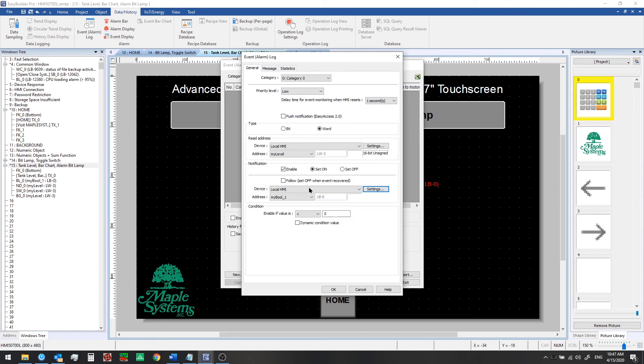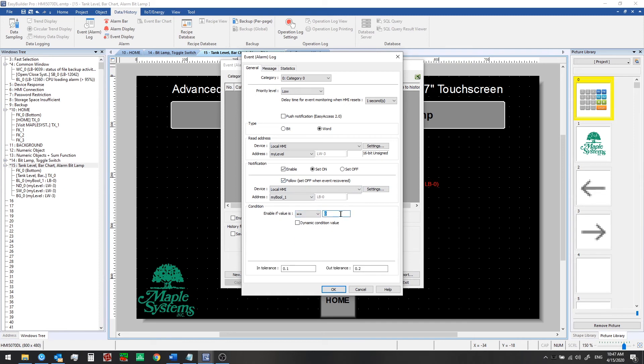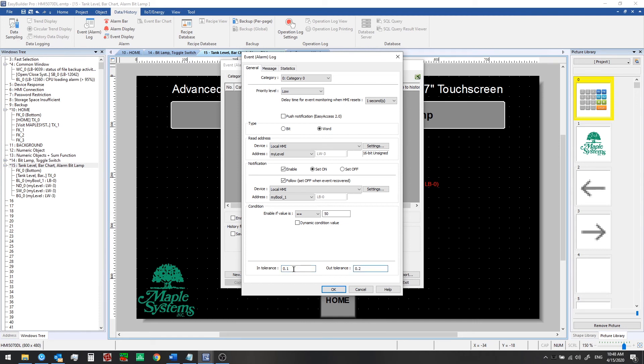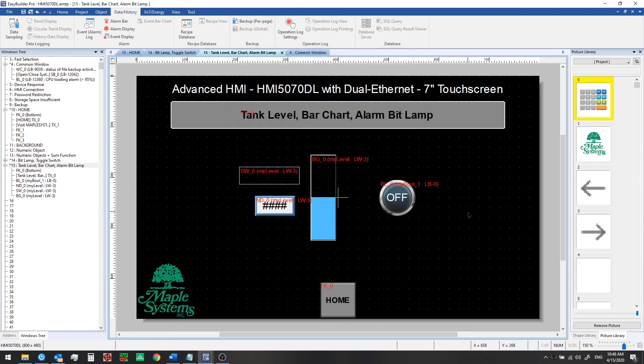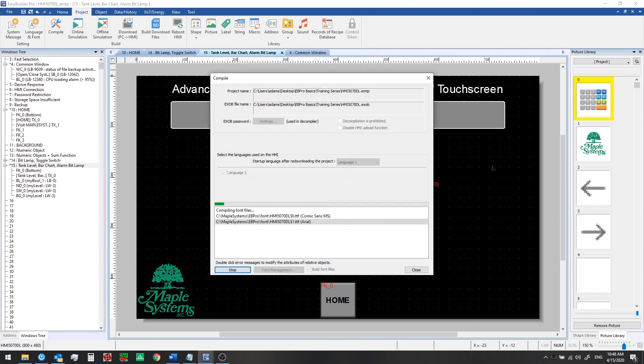So we will turn on this bit under the following condition. We'll turn it off again once that condition is no longer true. What we'll do we want to enable the bit if the value is equal to 50 and we have an intolerance and out of tolerance level. So below this if it goes back down it will still be on. If it goes above up to that point 50.2 it would still be on. We're going to change these to 10 and 10 so anytime the value of my level is between 40 and 60 that bit will go on and will be notified on this window that we're using. Let's go ahead and run the offline simulation again and we'll see how it works.